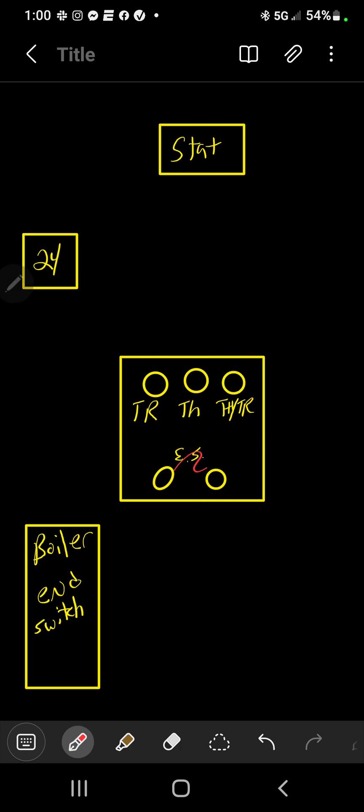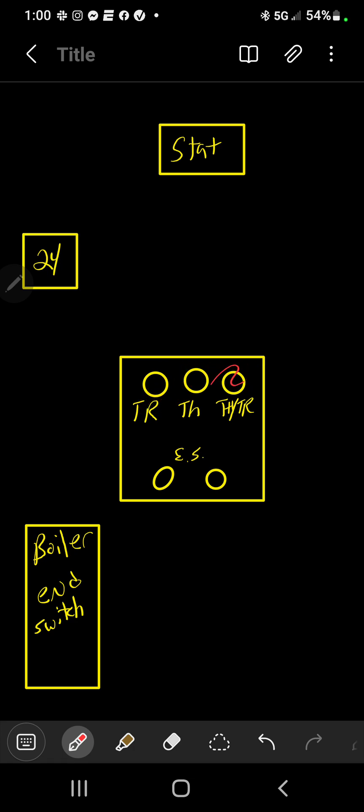So what we have on the screen is the actual zone valve here in the middle. We have our thermostat up here, our 24-volt transformer, and then the boiler end switch. Here's the zone valve. Your zone valve is going to have five terminals. These little circles are your terminals where your wires go into.